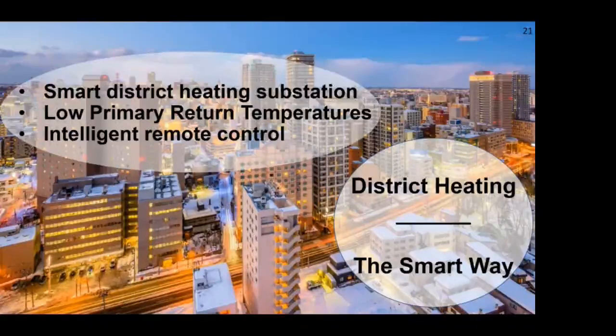It's not particularly cold today. Do you need to be flowing at 70? No. Can you get away with 60? Possibly. Can you get away with 55? And if you look at heat pumps, they're looking at flowing at 51, 52 degrees. But again, you've got to take into consideration, especially in a commercial building where hot water is required, how you can manage everything.